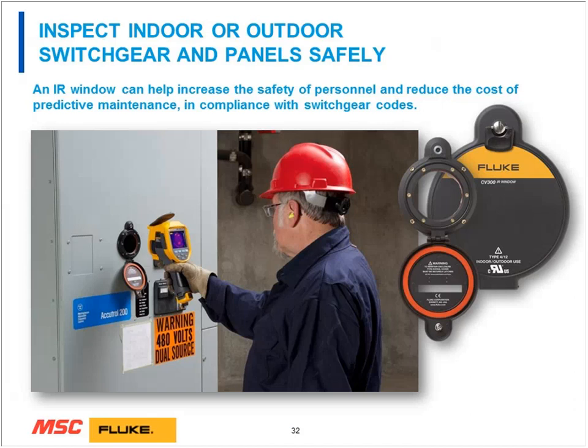Switchgear. I think IR windows, essential. If you have some switchgear, rather than opening the switchgear to make some specific measurements, if you're using thermal, definitely take a look at IR windows. Now, these are not glass. They're a special crystalline element that allows the transfer of thermal heat or thermal radiation through them, so they can be detected by the thermal imager. But once they're installed, and they only take a few minutes to install, then you can go in, open them up, take a quick scan of the panel to see if there are any problems, close them up again, and you're not exposed to the active power.